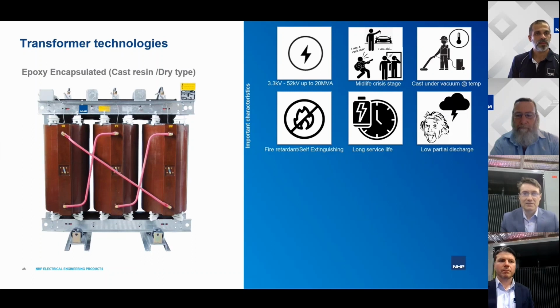Now, with the industry typical transformers, which are compliant to the requirements of the standards, the partial discharge levels go up to 10 picocoulomb. With the best technologies available in the market, though, you can achieve a low partial discharge down to 5 picocoulomb or less. And this indicates high quality of the resin, fewer impurities, fewer air bubbles, and so on. And that results, by estimates of our supply, in a longer service life by 3 to 5 years compared to a normal technology. And this is where the technological process is extremely important, and that is the know-how of the manufacturers, how to achieve that.